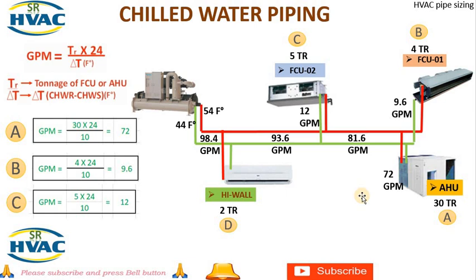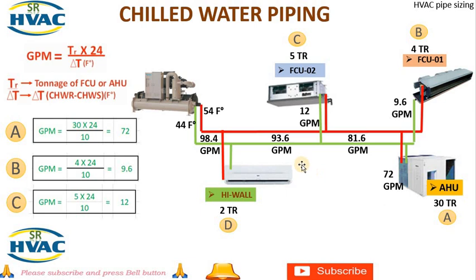The GPM for segment B will equal the sum of GPM for FCU1 plus the GPM of the AHU: 72 + 9.6 = 81.6 GPM. The GPM for segment A+B+C will equal the GPM of the AHU plus FCU2: 81.6 + 12 = 93.6 GPM. Including the high-wall unit at 4.8 GPM, the total becomes 93.6 + 4.8 = 98.4 GPM.